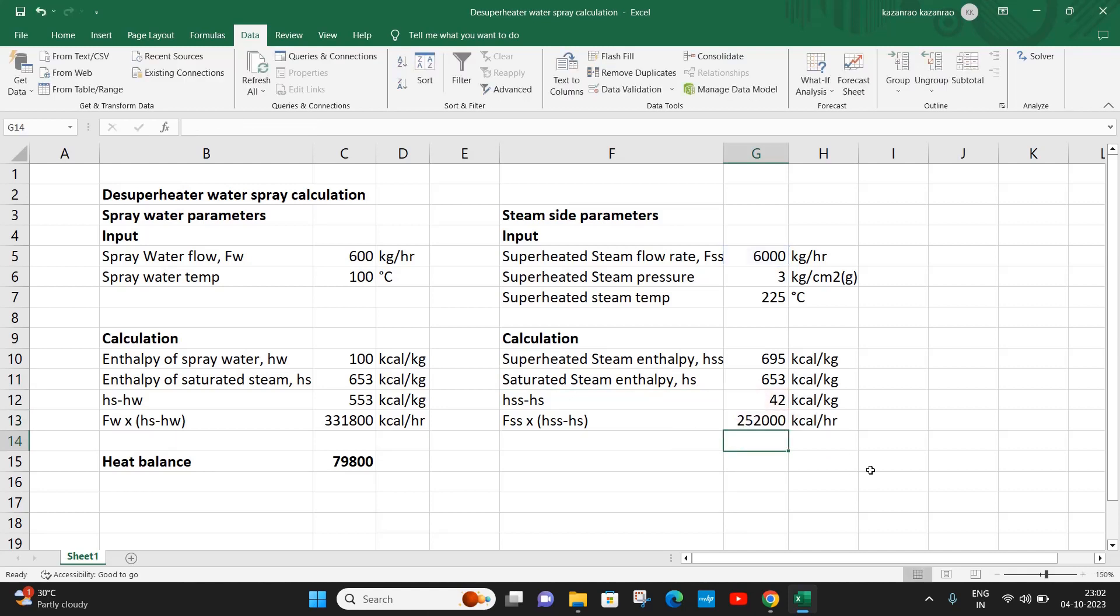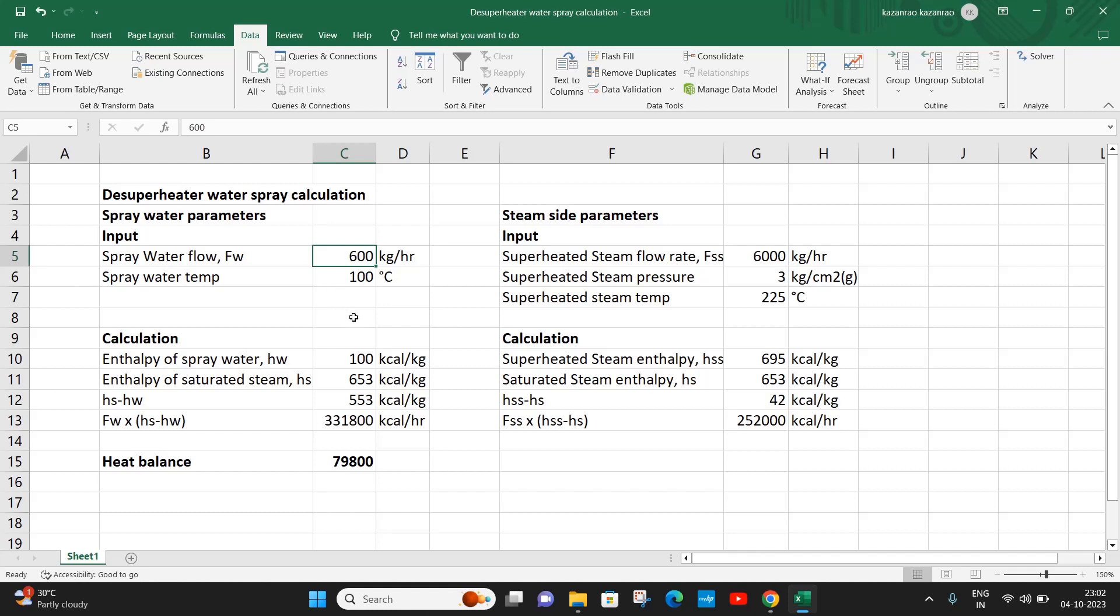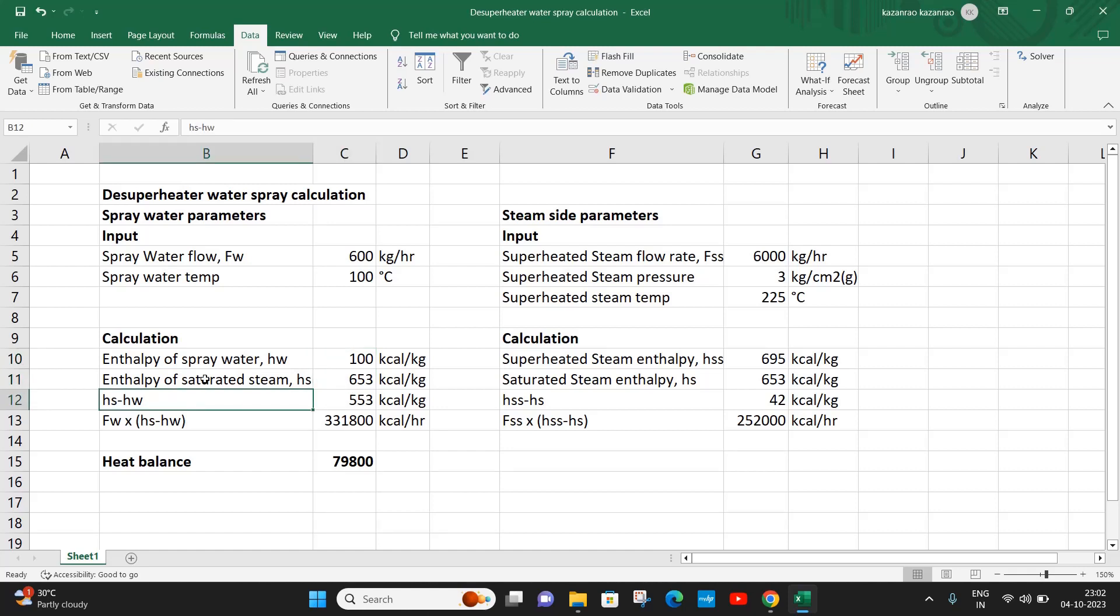Now let us consider that the spray water is at 100 degrees Celsius. The water flow rate of 600 is only an assumed flow. We have to iterate this value so as to exactly calculate the amount of water spray required. At 100 degrees, the enthalpy of spray water is 100, and enthalpy of saturated steam is 653.